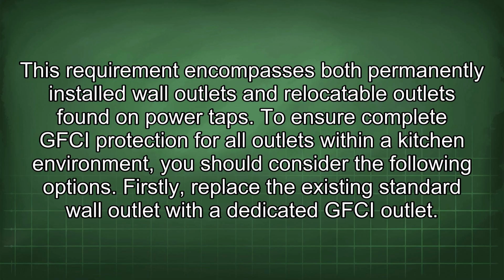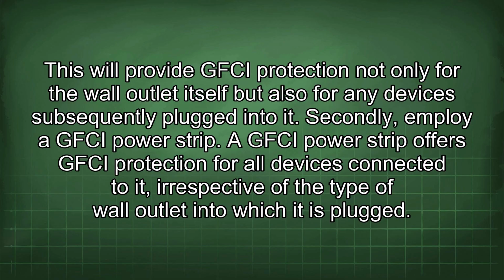Firstly, replace the existing standard wall outlet with a dedicated GFCI outlet. This will provide GFCI protection not only for the wall outlet itself, but also for any devices subsequently plugged into it. Secondly, employ a GFCI power strip. A GFCI power strip offers GFCI protection for all devices connected to it, irrespective of the type of wall outlet into which it is plugged.